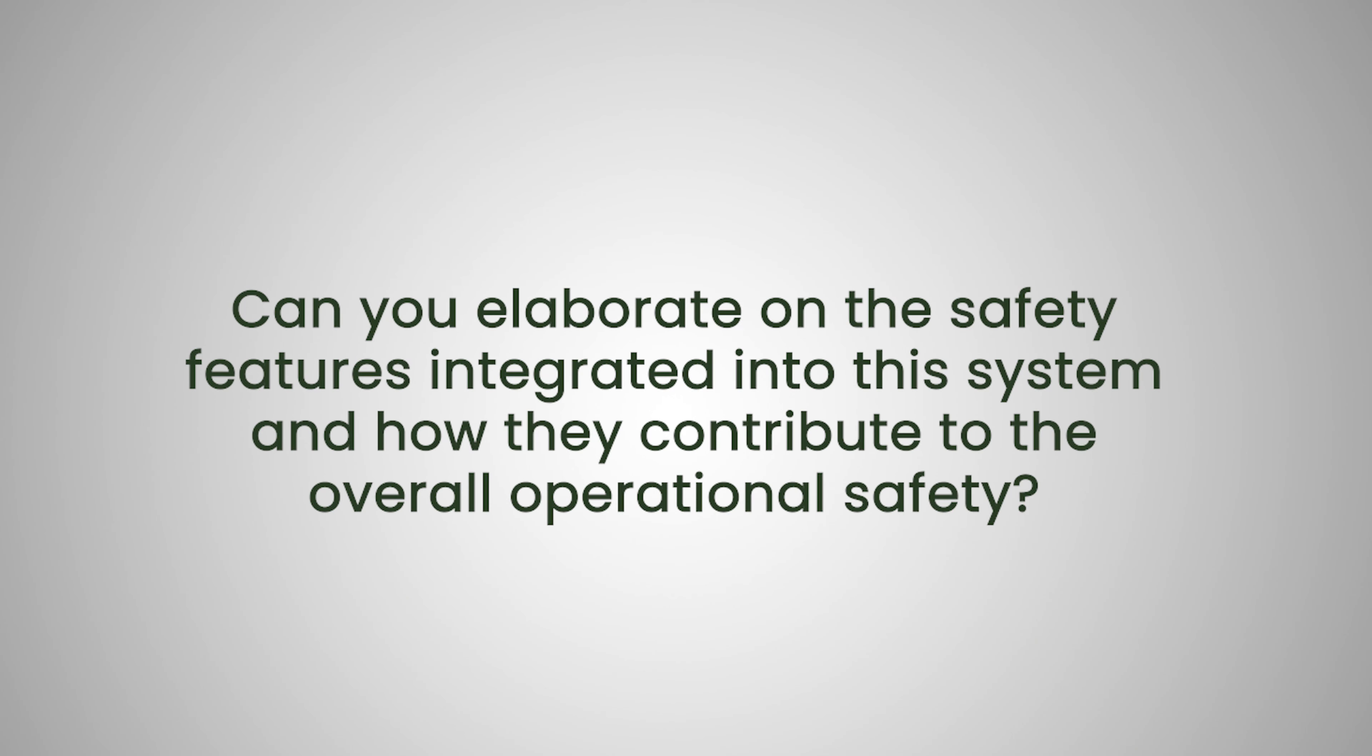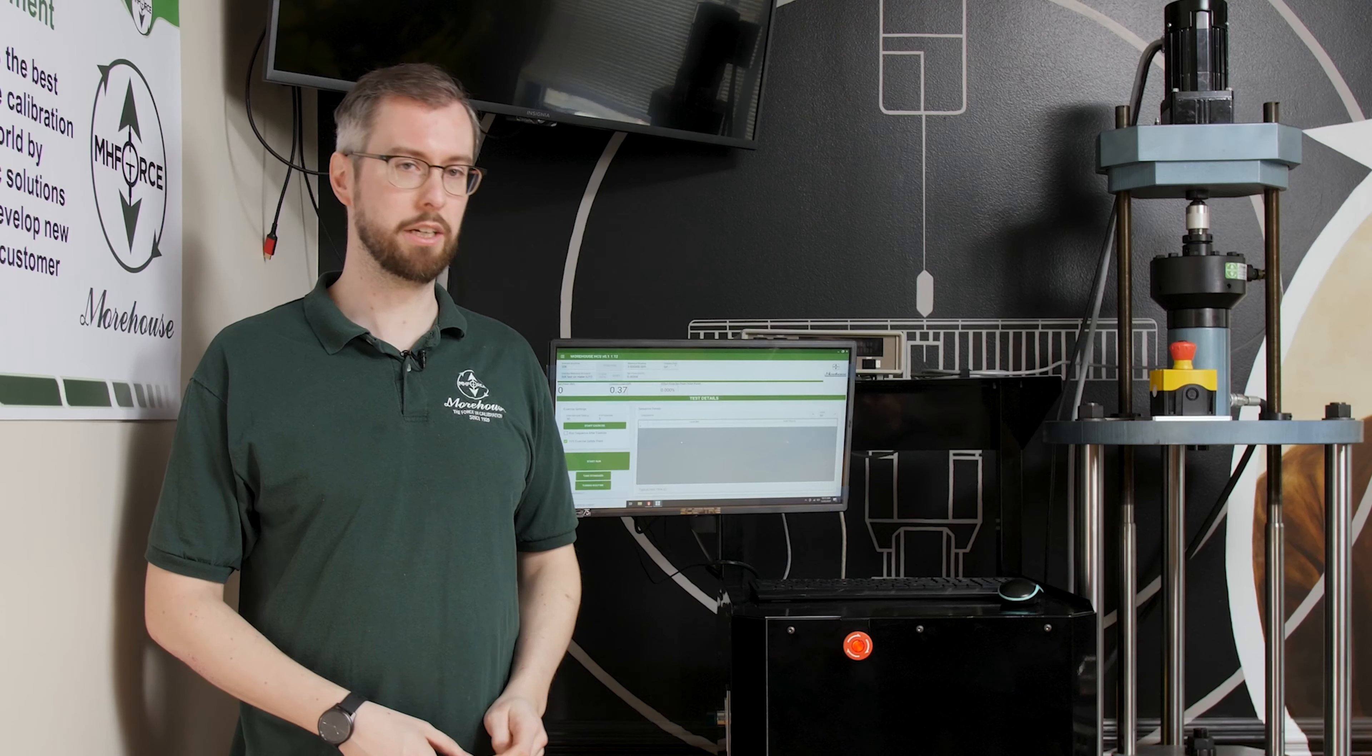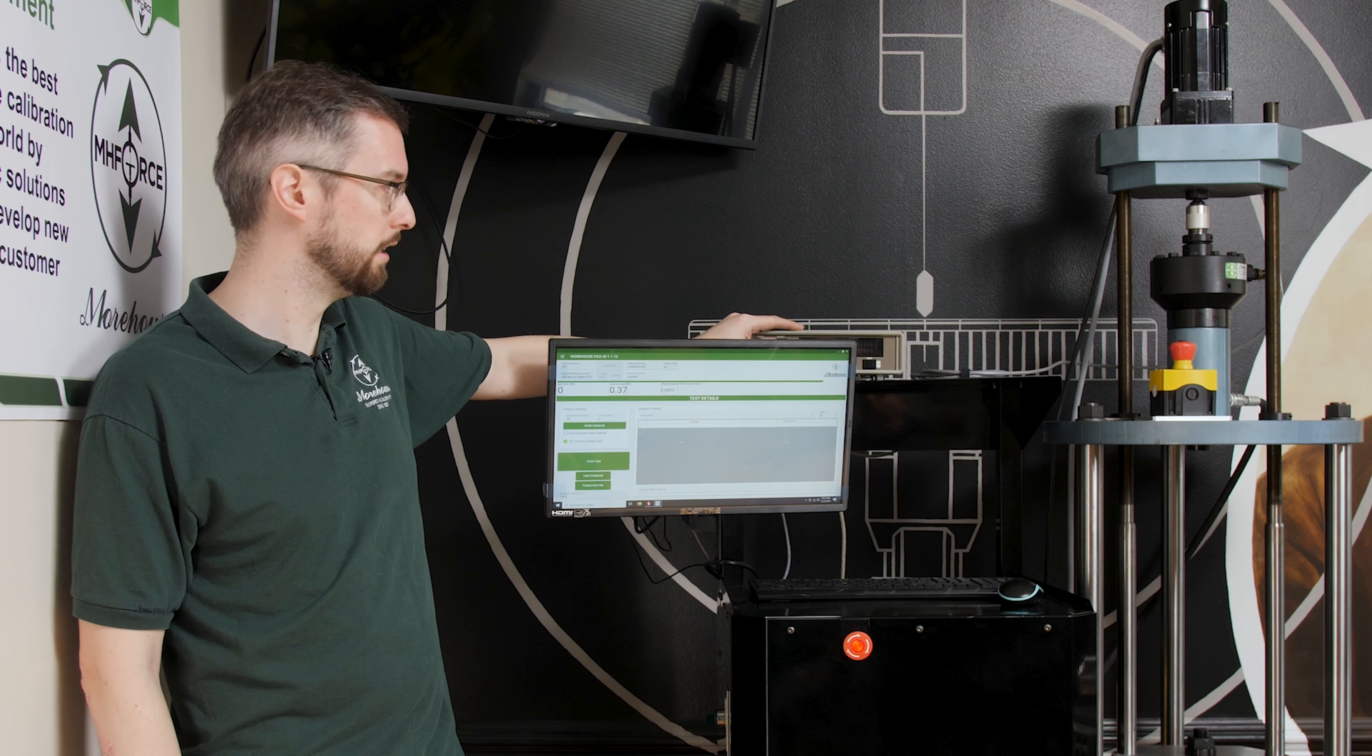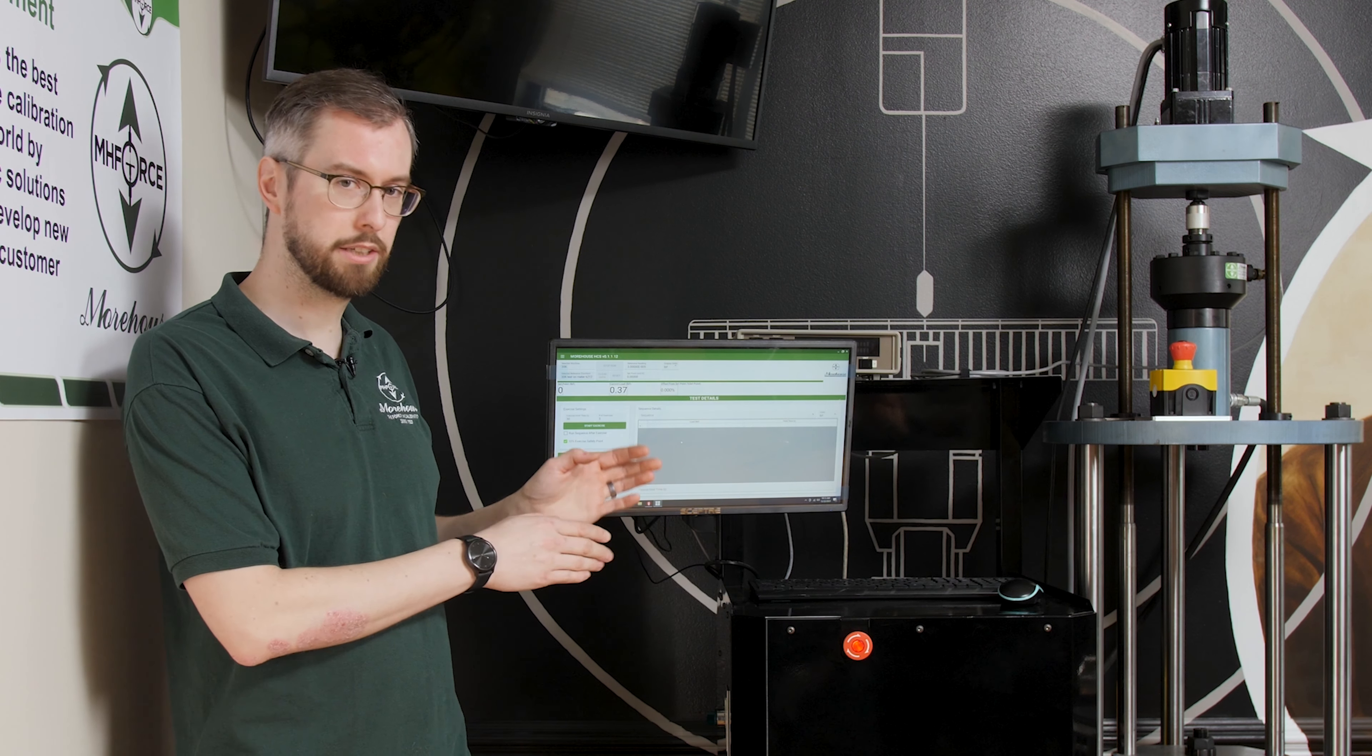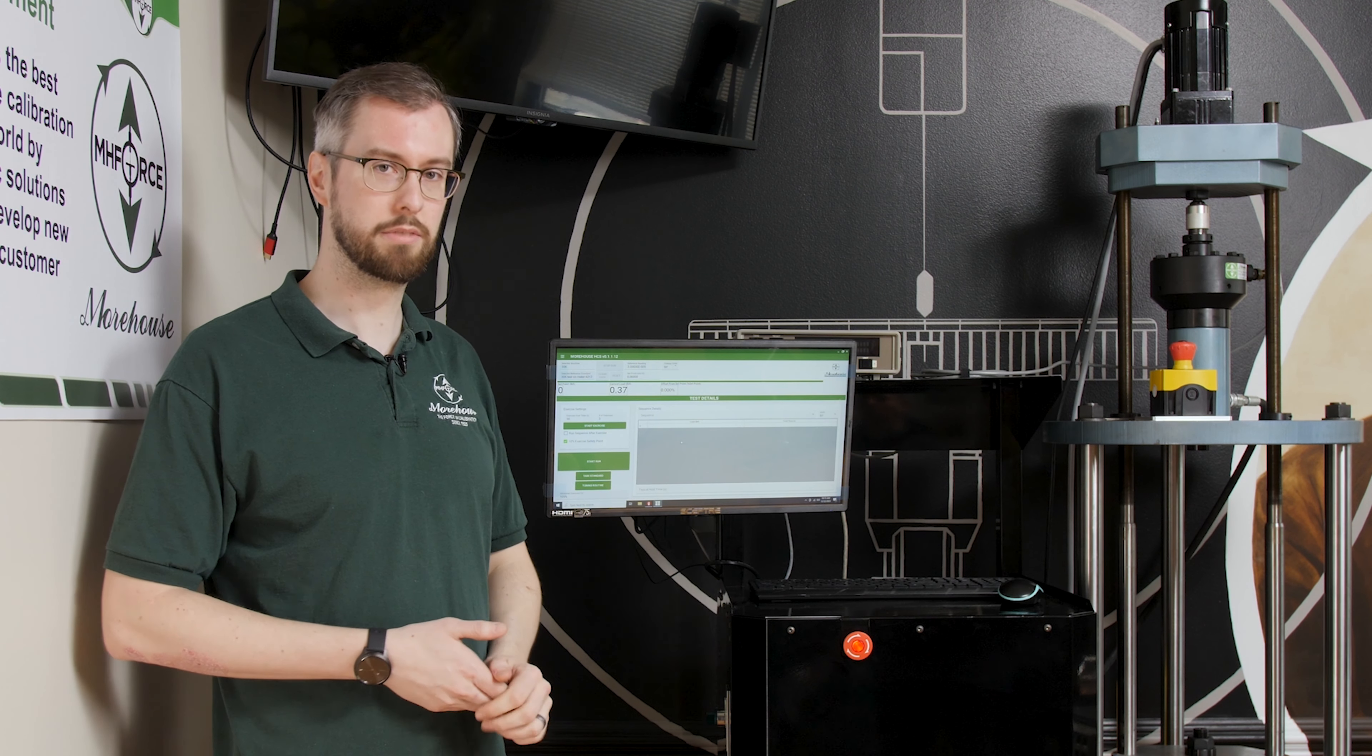Can you elaborate on the safety features integrated into this system and how they contribute to the overall operational safety? We built a lot of safety features into the unit. There are two manual e-stops, one on the front of the cabinet and one that can be mounted on the machine. So if anything goes wrong, the operator can hit that. There are also several automated safety features. So the reference standards meter can shut the system down if it goes over a certain millivolt per volt value. And that's configured at every run. So it'll set to shut down when it goes over capacity on the DUT as well. There's a pressure sensor inside of the cabinet that's checking to make sure that the pressure that it sees in there matches what it expects from the load cell. So if you don't have a load cell connected or the wrong reference standard, it will stop running.